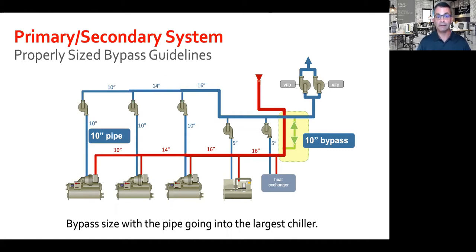You'll see here it's between the supply manifold and the return manifold. In this case, the bypass is 10 inches. The chillers here are identical and all have 10-inch lines, so these pipes were selected well. Again, it's worth repeating that it is critical to make sure the bypass line is sized correctly. Next slide, please.